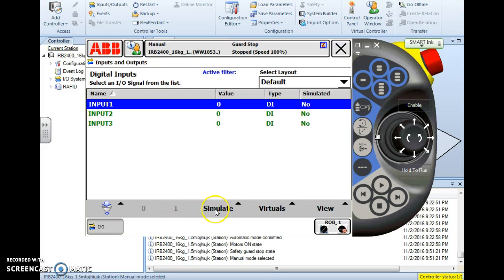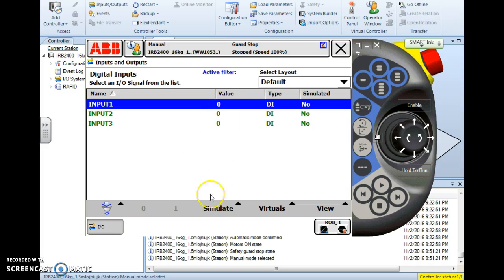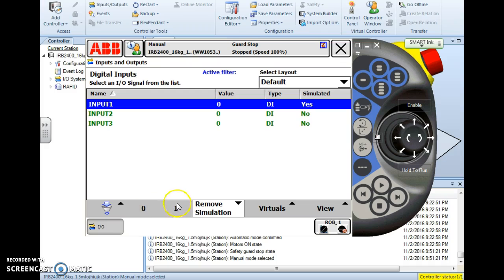Now remember, when I simulate an input I am not physically changing the state of that input. I'm basically tricking the controller into thinking the input is on or off. To simulate it all I have to do is hit the simulate and choose the state that I want it to be simulated.